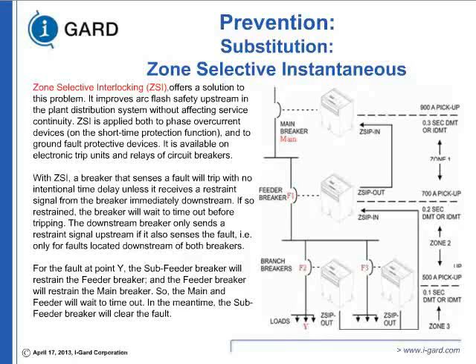You can do the same kind of zone selective interlocking with current limiting fuses. Of course, the fuse manufacturer will tell you what the minimum rating or coordination rating should be. Some may be 4 to 1, 6 to 1, and so on. So if you're using current limiting fuses or other fuses and you want to coordinate, I suggest you talk to the manufacturer about what the coordination ratio for that fuse might be.